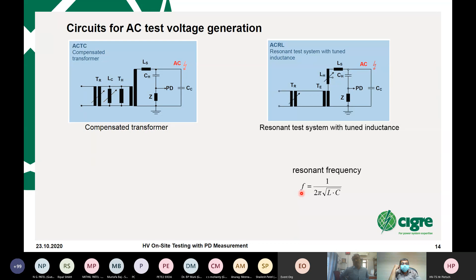The other one is the tuned resonant test system. And here the equation is very simple. For the after-installation test, you have to have 50 or 60 hertz, because the cable or the GIS capacitance will change. And if you have a fixed inductance, then of course the frequency will change, and this is not allowed. So one possibility is to change the inductance, and this is shown here. Depending on the capacitance of the cable, the frequency can be adjusted to 50 hertz.